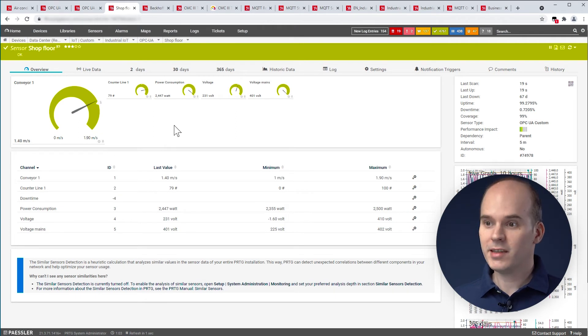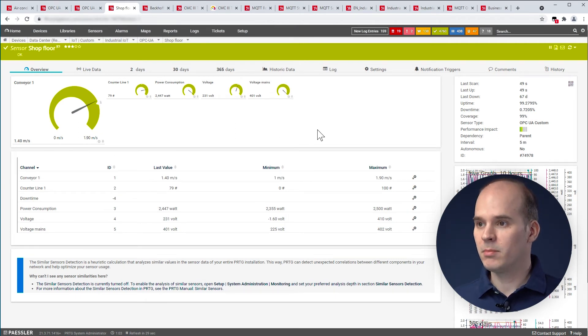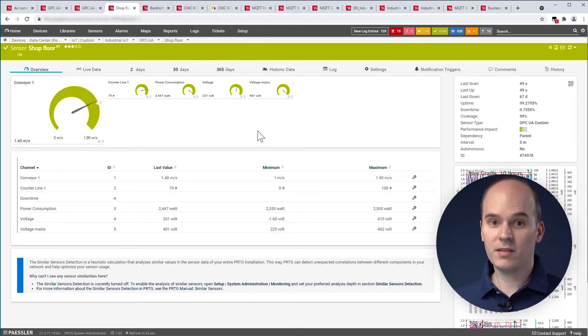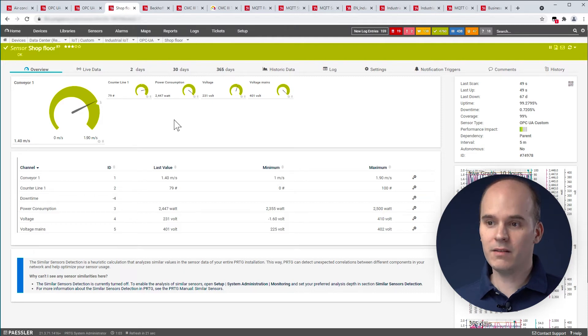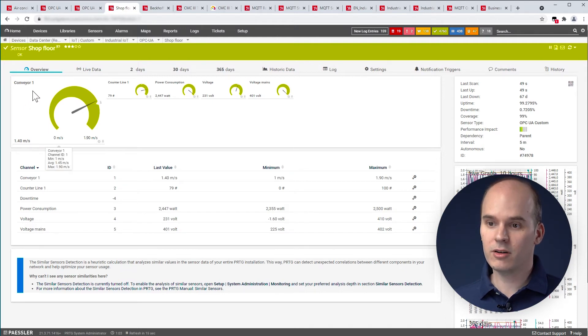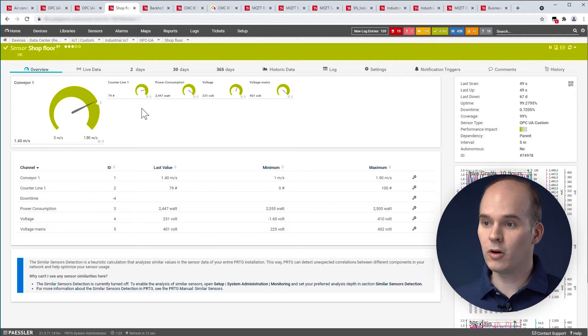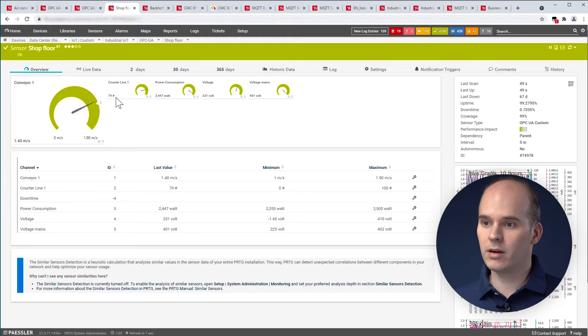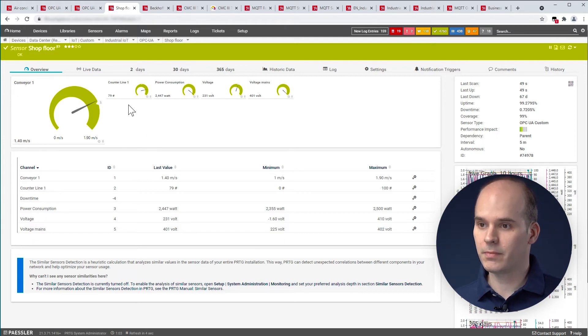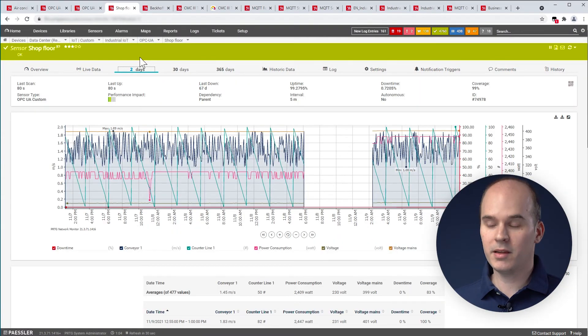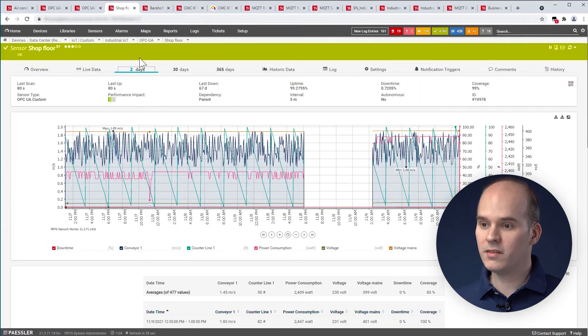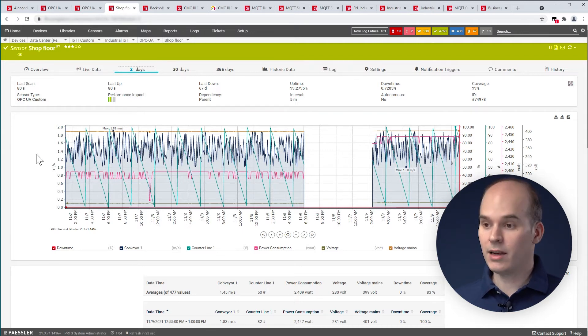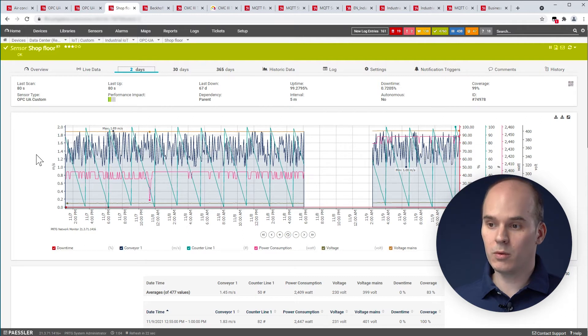In this example, we see a more generic sensor. It's called the OPC UA custom sensor. With this custom sensor, you have the possibility to get any information from the OPC UA server. For example, the speed of the conveyor you can see here in meters per second or other information about the shop floor like the voltages or the counter line. In the upper area, we can create a diagram, for example, in this case two days. And then you can see how the data was in the past, if there was a failure and what it was and how to fix this.